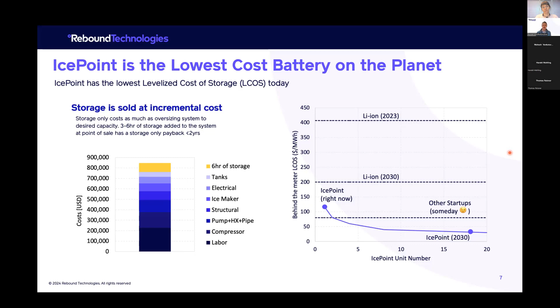Right now, today, our levelized cost of storage behind the meter, in a diurnal one-charge-a-day, one-discharge-a-day kind of operation, is $120 a megawatt hour, which is phenomenally low, especially for a first commercial scale system. We still have a ton of value engineering and system improvements to implement to drive that down further. Our current costs are extremely low for our storage, and obviously they're only going to get lower as we build more and more units.